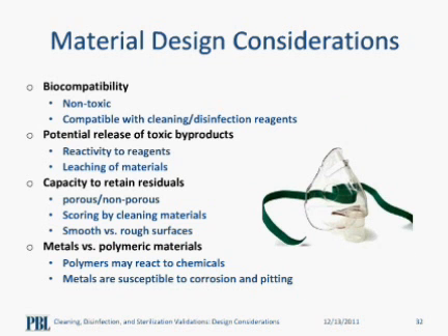Smooth materials are preferred compared to rough surfaces for easy cleaning. Some materials are prone to scoring caused by the cleaning tools used. A good example of this is the metal ends of brushes that scratch the device surface. In effect, this can contribute to retention of residuals and tissue penetration, which makes cleaning more difficult.